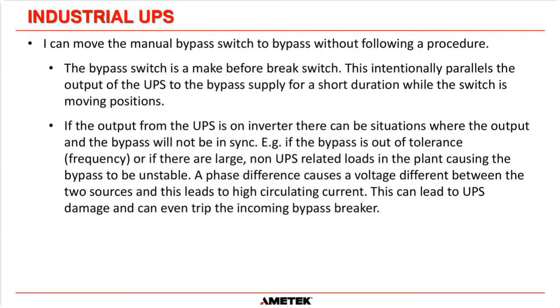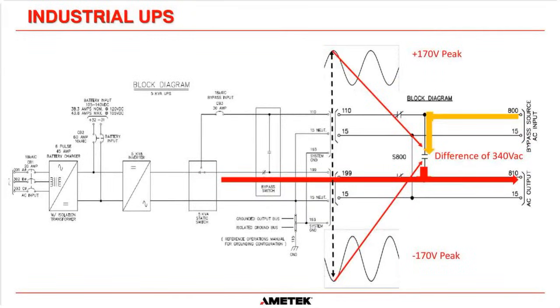If you've just moved the bypass switch from normal to bypass, and in doing so, you trip the incoming bypass breaker, well, you can guess what happens there. The bypass breaker trips and you go to bypass, you've dropped the load. So do not move the bypass switch to the bypass to load position while the inverter to load static switch is on. And this next slide should help you see that, okay?